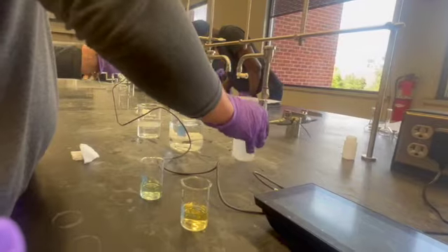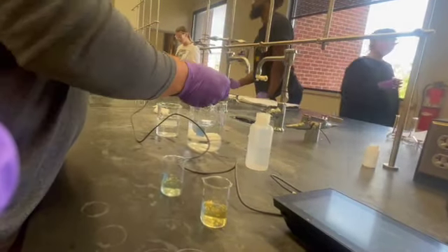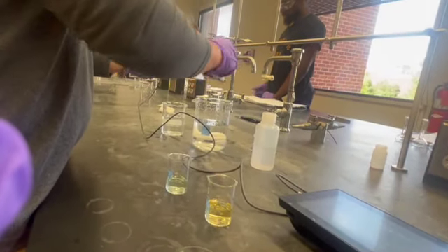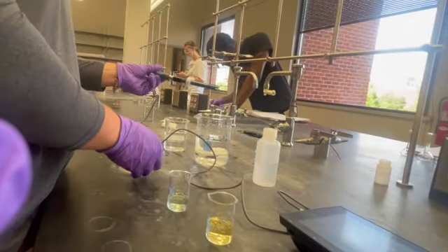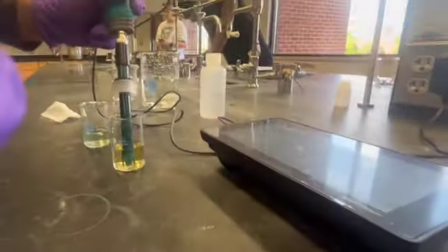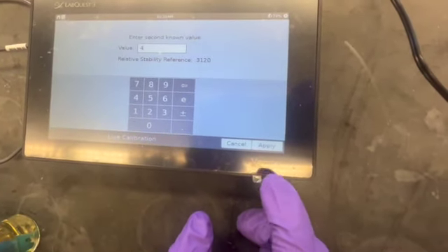Before testing the pH 4 buffer, rinse your probe with the deionized water into a waste container and blot the excess water with a Kimwipe. After blotting the probe, place it in the pH 4 buffer. Wait for the meter to stabilize, then press 4 and enter on the pH meter. The meter should be reading correctly at 4.0.